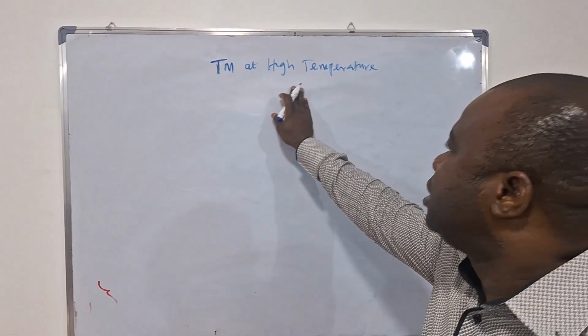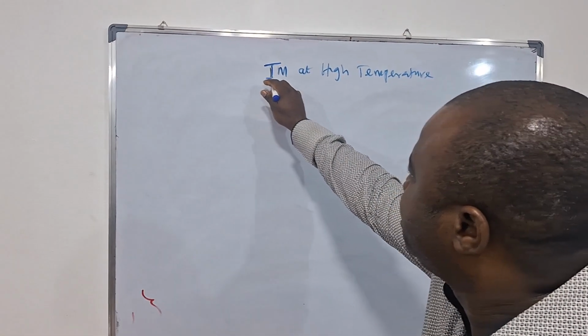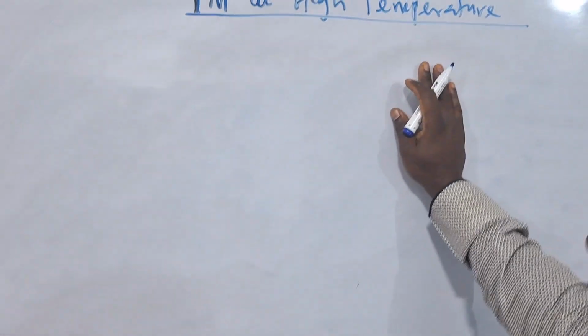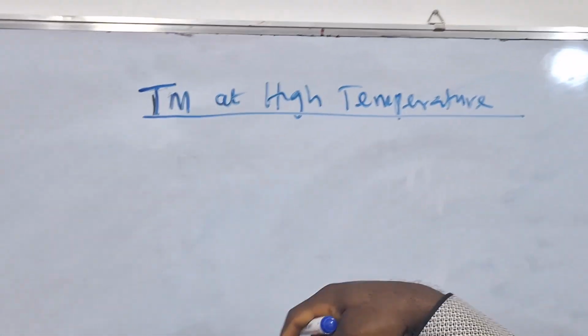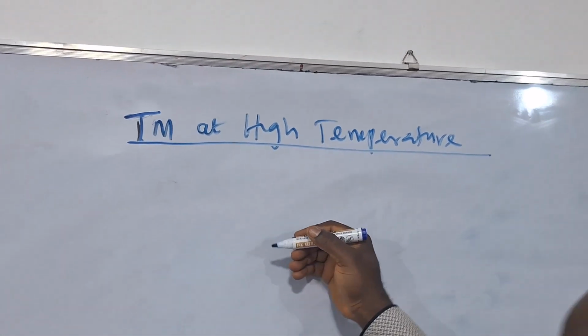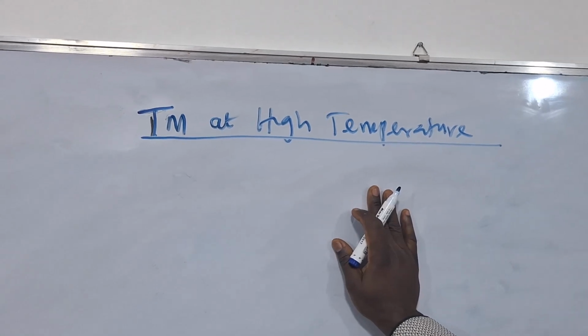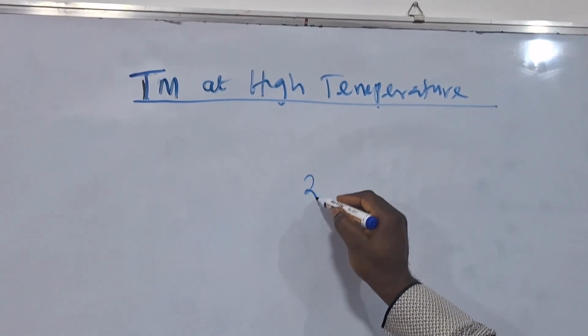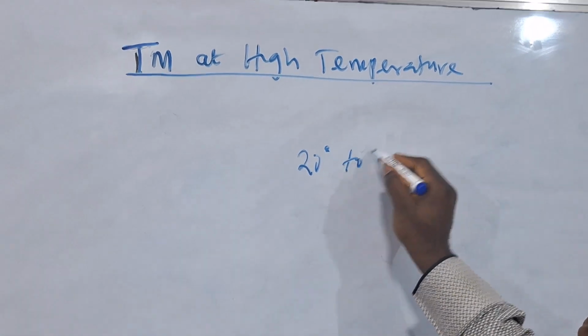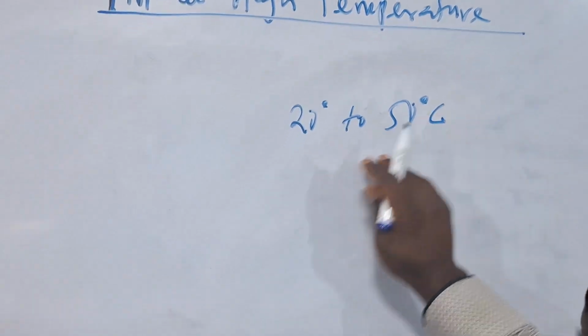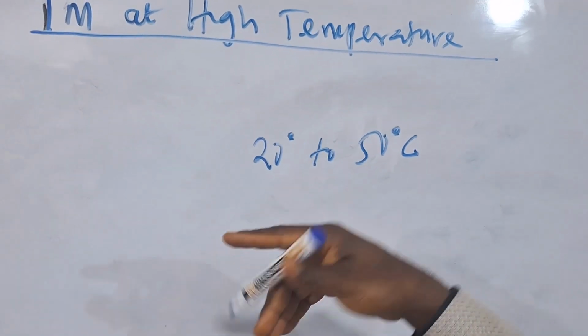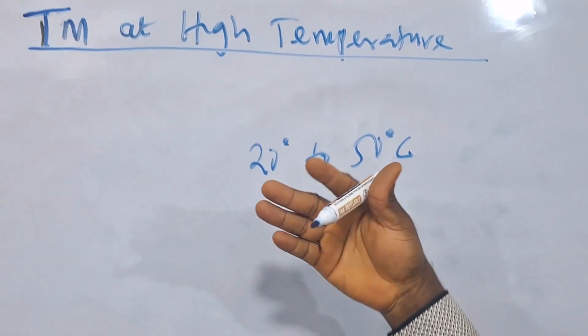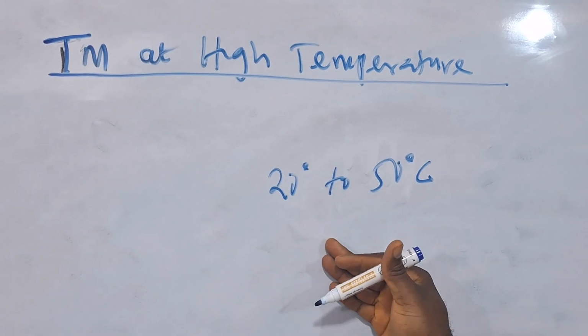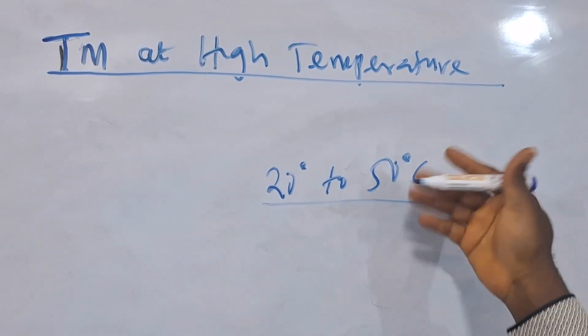So we'll look at taking a thickness measurement at high temperature. By design, most of your probes will normally operate between 20 degrees Celsius to 50 degrees Celsius, which is your normal atmospheric or room temperature, depending on where you are.